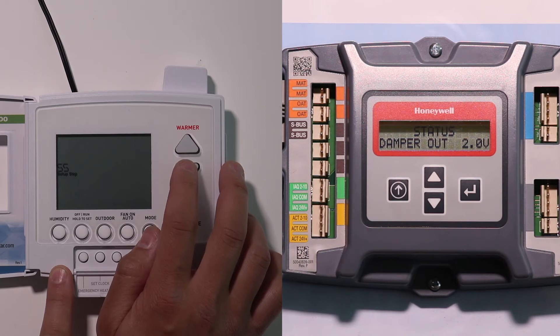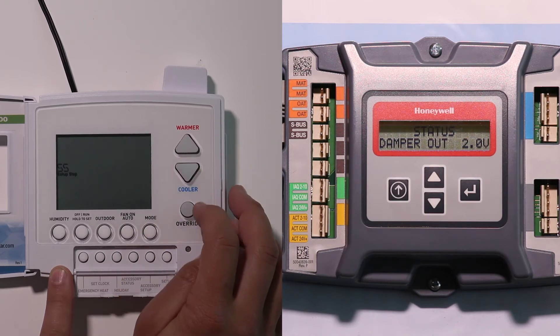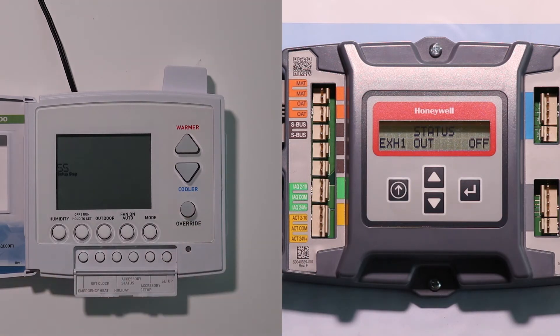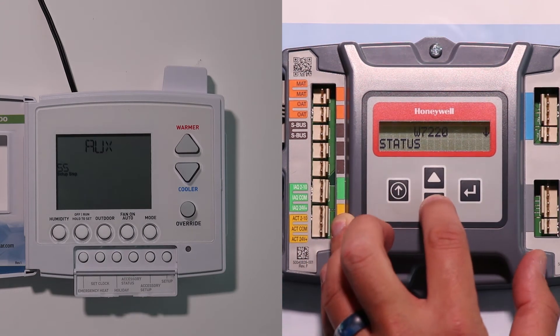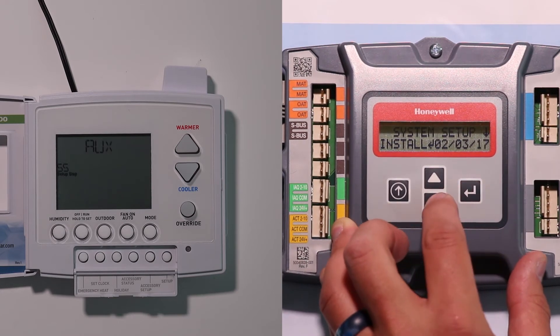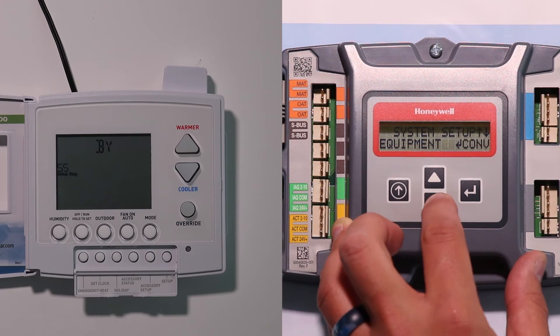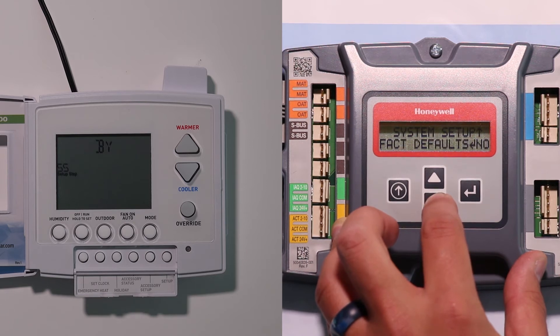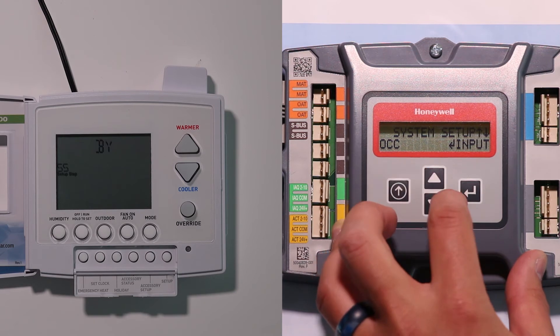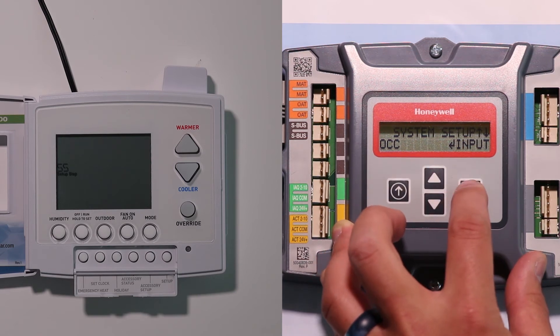Then over on our economizer controller, we need to tell him to accept this signal. So the way we're going to do that is we're going to go through this guy and go to the system setup mode, hit enter, and we're going to scroll down until we get to OCC. So on that one, our choices are input or always, and we want to have him set up for input on there.